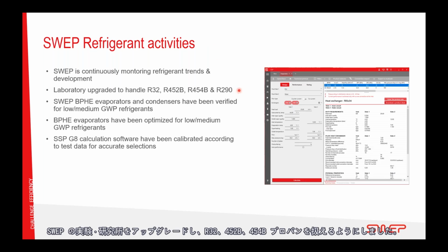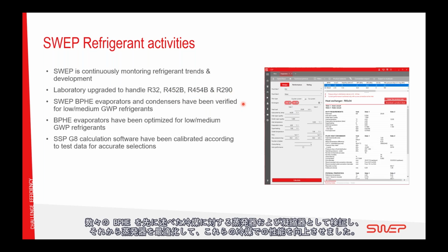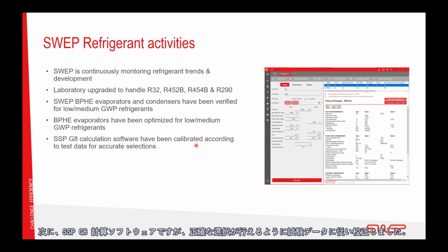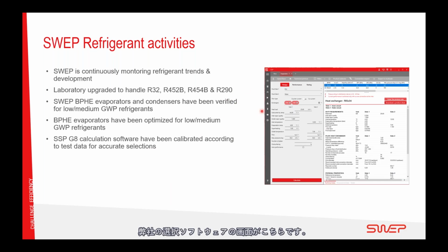We have upgraded the laboratory in SWEP to handle R32, R452B, R454B, and propane. We have verified a number of BPHE as evaporators and condensers for the above mentioned refrigerants. And then we have also optimized evaporators to better perform with these refrigerants. Then the SSPG8 calculation software has been calibrated according to test data for accurate selections. And here you can see a screen from our selection software.